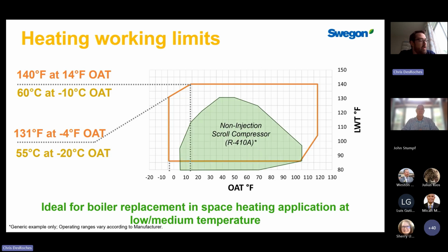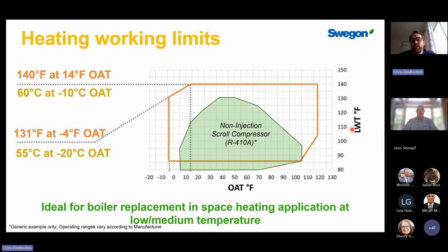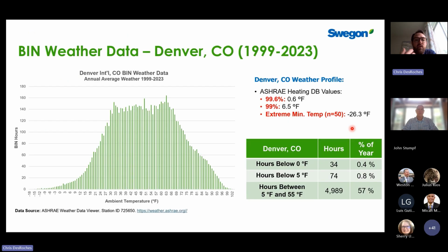We compare this to equipment that was on the market 2-3 years ago without injection technology. With what I would call low lift compressors, we're not able to generate those high temperatures, so there is a very steep drop off in the supply temperature as it gets colder outside. So that is not terribly useful to heat our building through all the colder winter hours, but with liquid injection compressors, the technology is closer in performance to condensing boilers, so that's where the fit is.